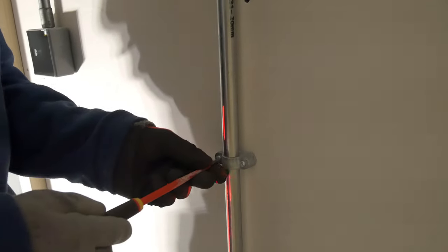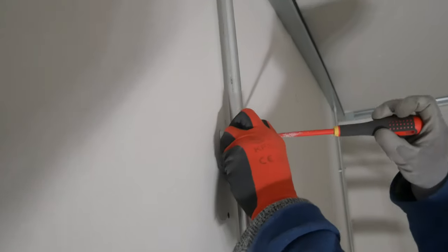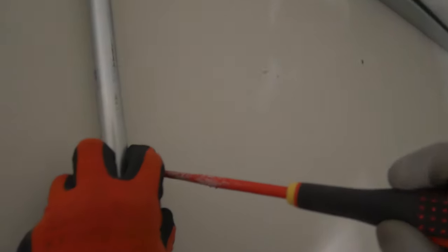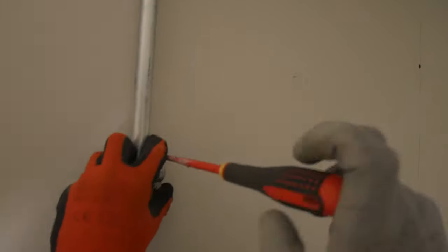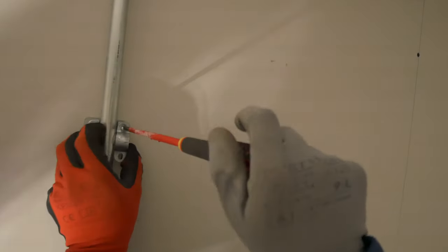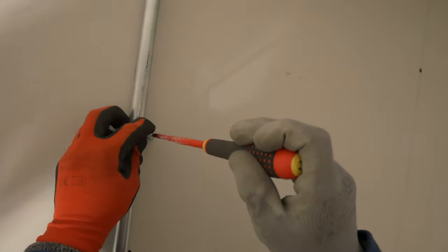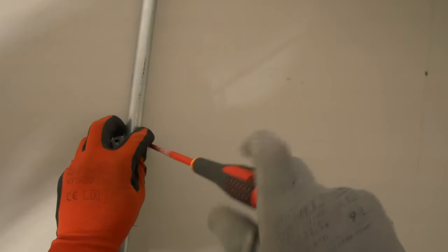Now you see with these, once you do come to connecting your circuit accessories, there is lots of earth connections within this containment system by default. So you're going to want to think about the earthing arrangements on the containment itself. Now with this one, it's not forming any part of being a circuit protective conductor, because you can set the circuits up in that way as well if you wish, but it will by default become an extraneous conductive part. So we need to think about that, and we'll have a little look in the books and speak about that later in the video.